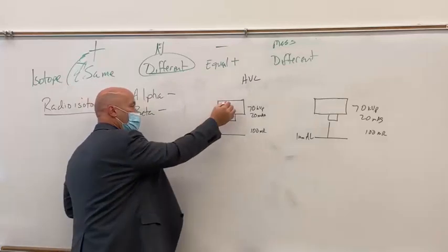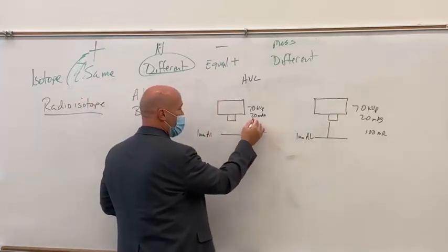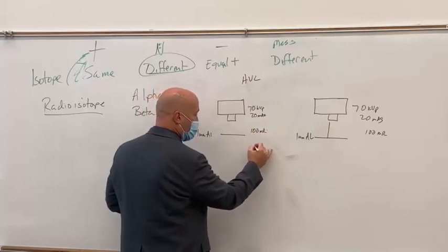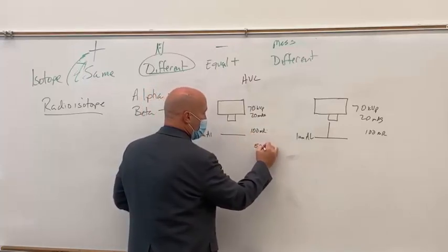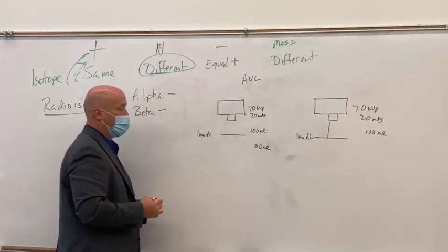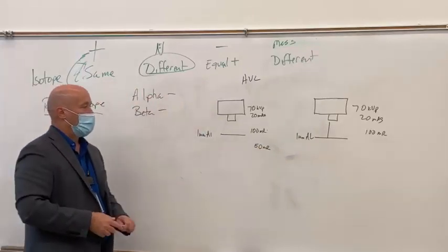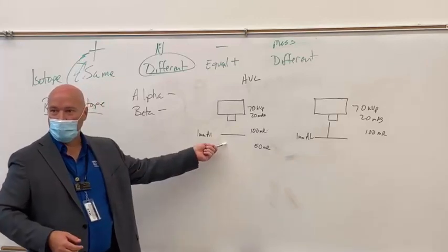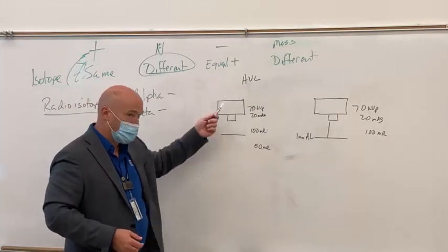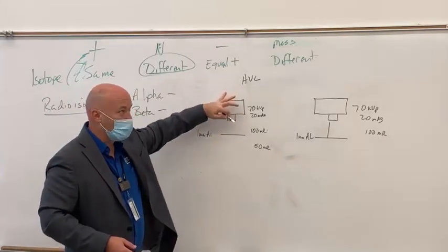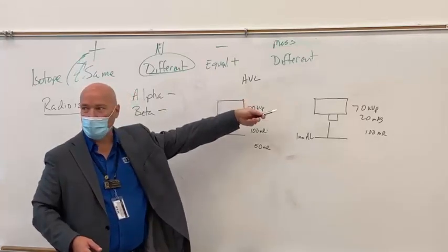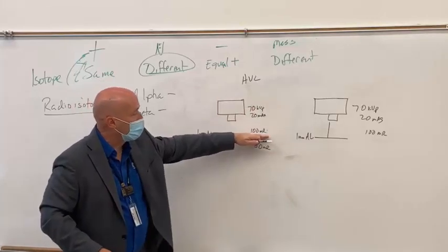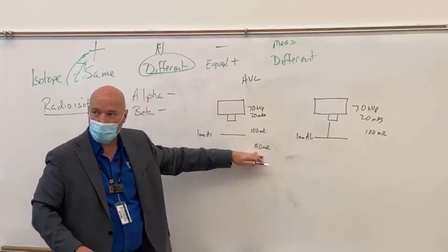And let's say you energize this X-ray beam and you measure the mR before the aluminum and the mR after the aluminum. And after the aluminum, you've got 50 mR, then what can we say about that 1 millimeter of aluminum? It is this X-ray beam's, or this room's, half value layer, right? Because it cut the intensity by exactly 1/2.